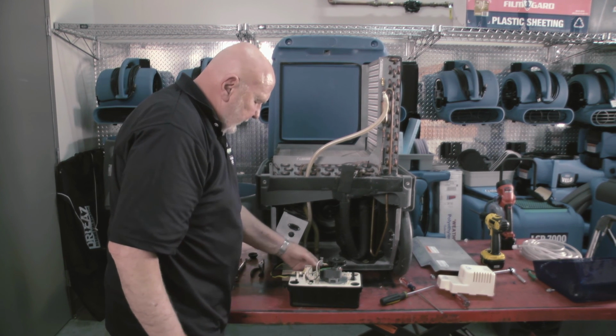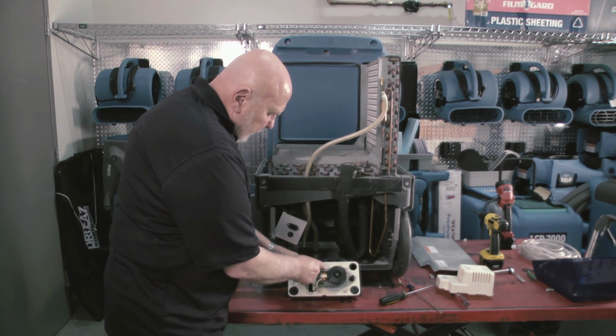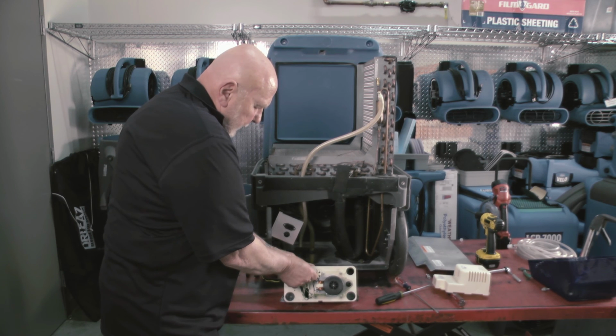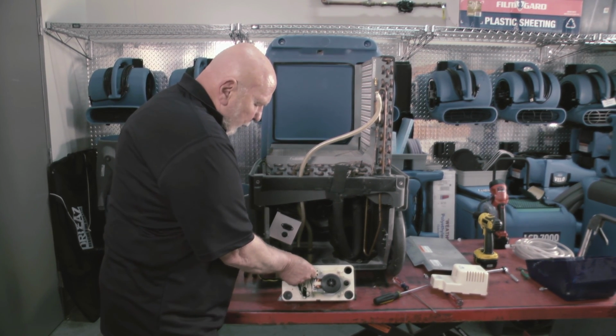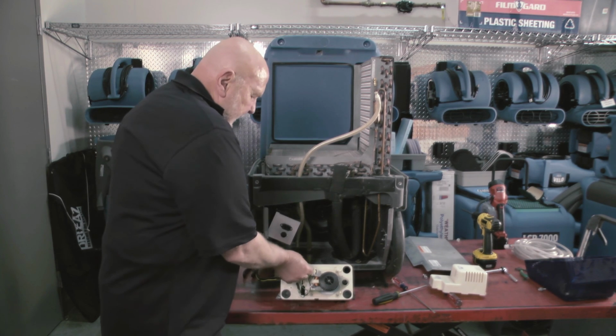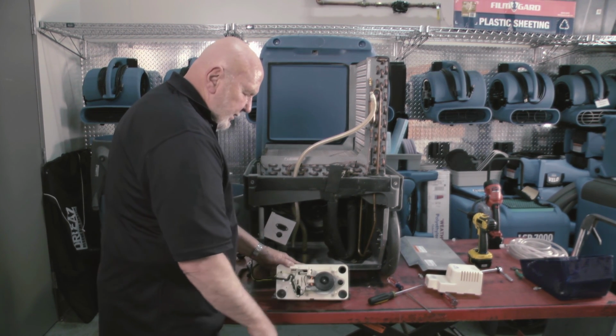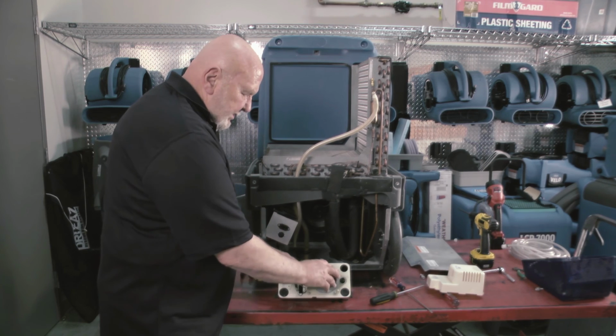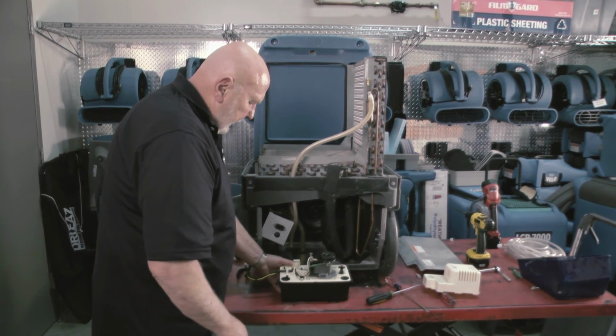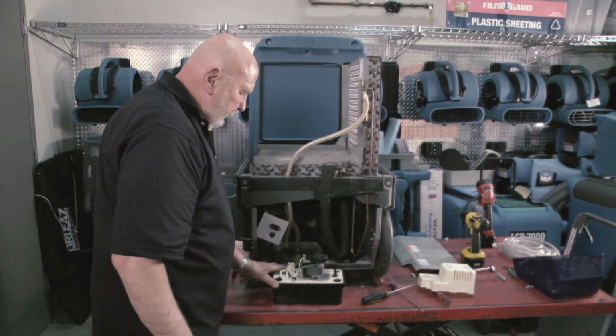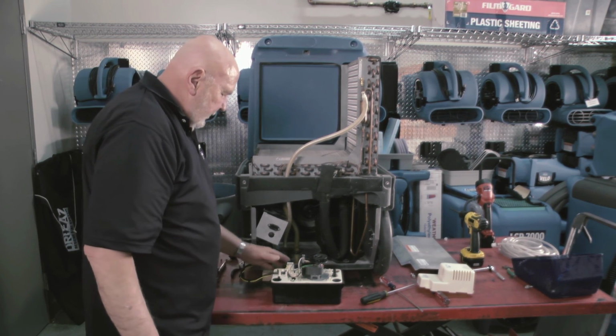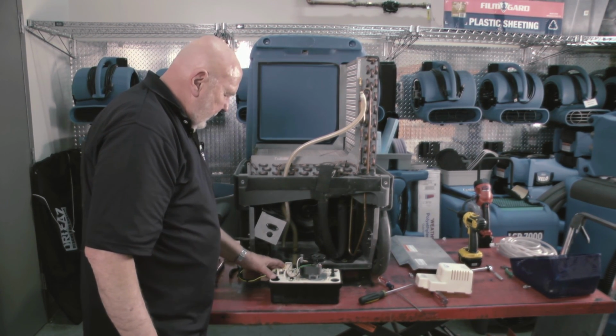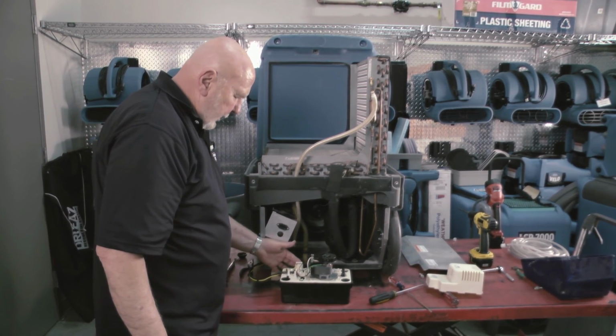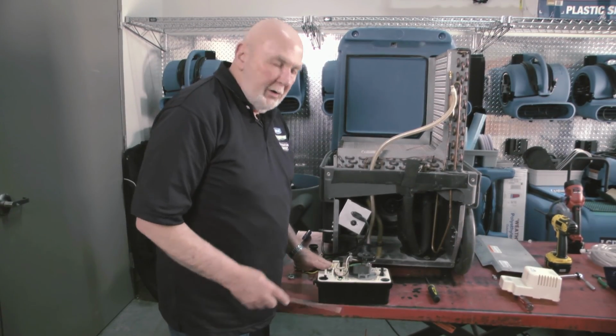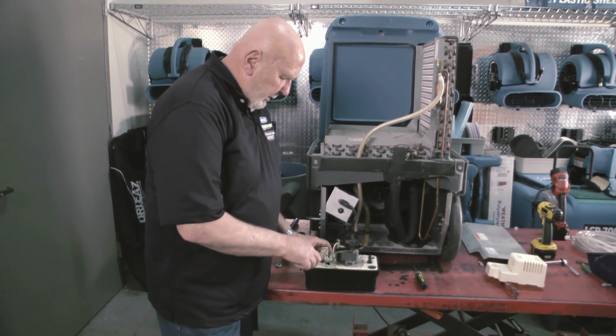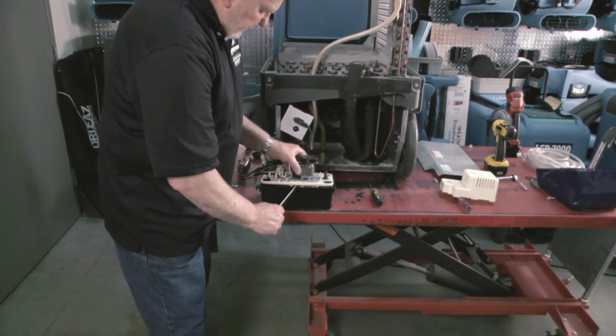I want you to pay attention to the float switch here. I want you to listen to it. I maybe want you to plug the unit in and see if, when you lift it up, this actuates the blower or the motor. This is the blower that sits on the motor. This end of the pump is normally okay, but sometimes the float switch can fail, and it's essential that you pay attention to it. The next thing that you want to do is actuate the basin on this pump, or look at it, I should say.